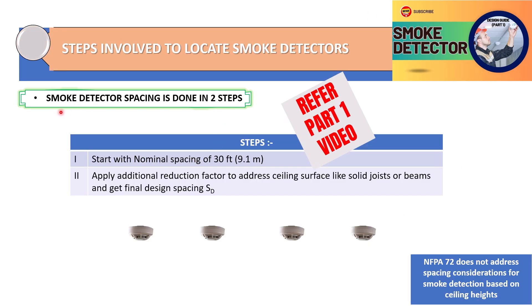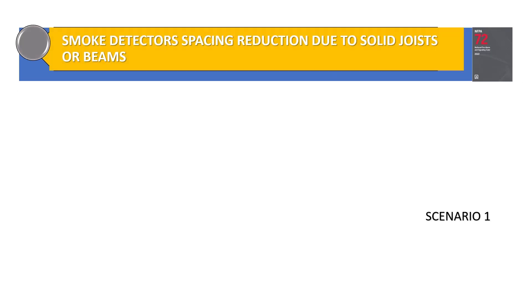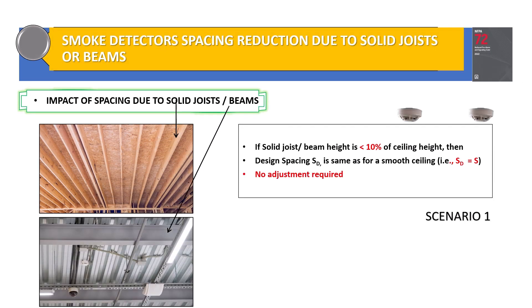Let us have a thorough recap of smoke detector spacing. It has to be done in two steps. Number one would be the nominal spacing, which is 30 feet. However, this nominal spacing has to be reduced — we need to apply a reduction factor based on some scenarios, such as when the ceiling surface has solid joists or beams.